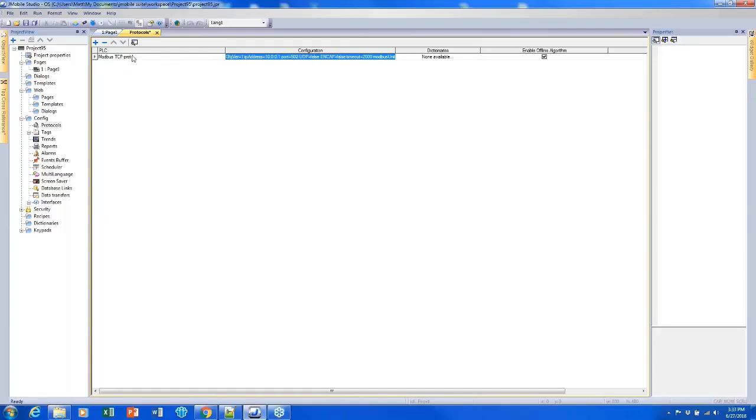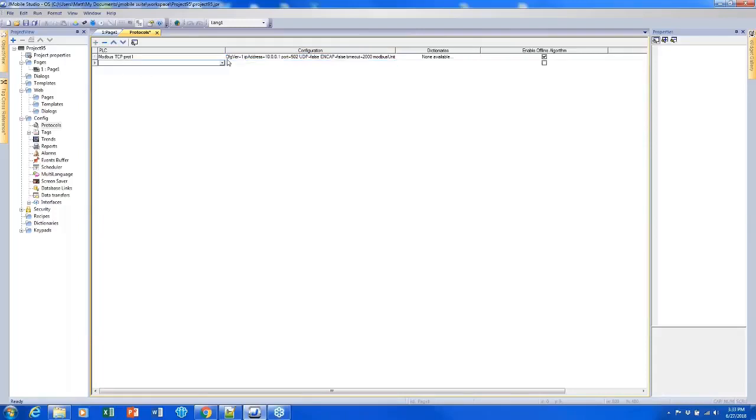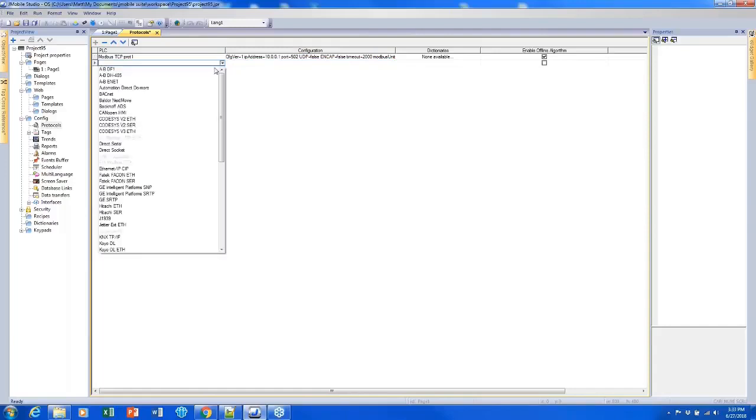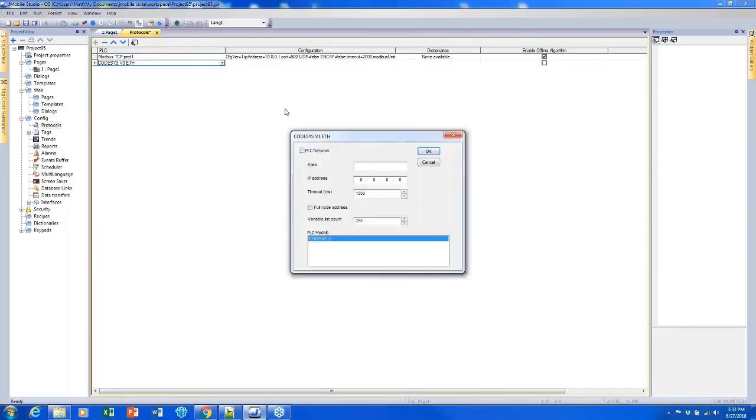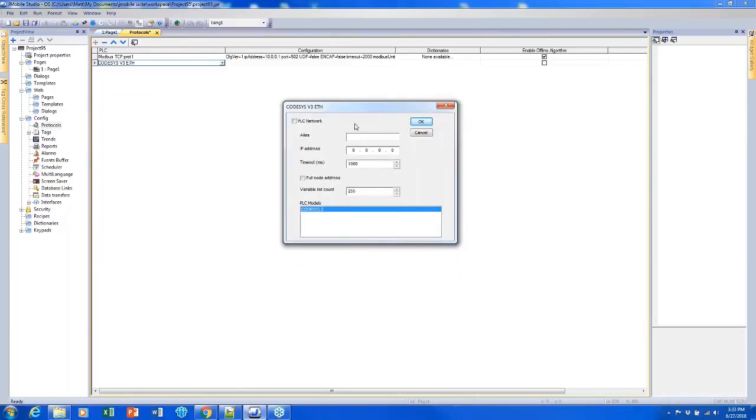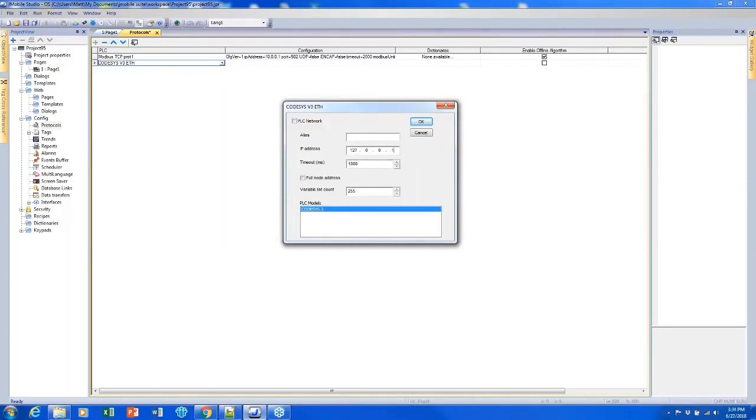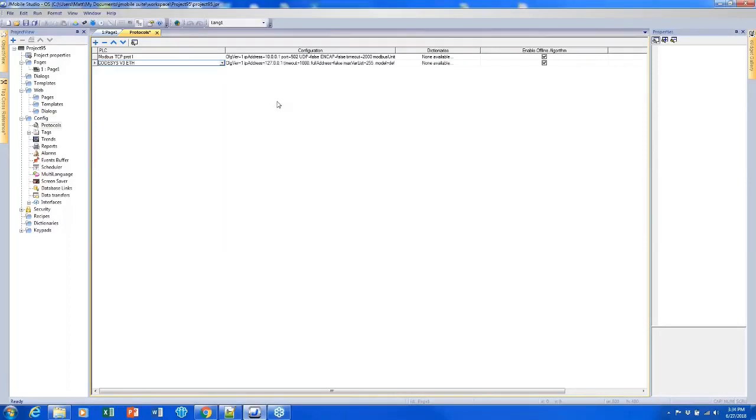So the first one being Modbus TCP, and another one could be a different type of PLC, or it could even be CODESYS, which I'm going to add next. So CODESYS, even though it does reside on the HMI, it does require us to use one of our four external protocols. So to set up CODESYS, we simply enter in the local host IP address and click OK. And we've got it set up.